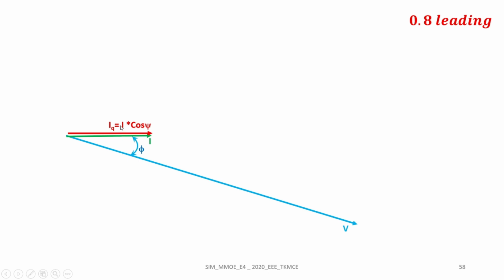Then we need to consider the various drops. Here only one drop is available, that is IQ SQ. The Iq Xq drop is drawn from the tip of the V phasor, leading IQ by 90 degrees. So this completes the phasor diagram corresponding to this situation. Here it is to be noted that psi is 0, that is the angle between E0 and I is 0, and the angle between E0 and V is delta. Please mark the different parameters in this phasor diagram.